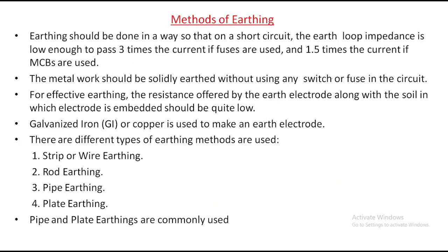Next, methods of earthing. In our electrical system, we generally have a number of methods. We will discuss each and every method. First method: earthing should be done in a way that the short circuit and earth loop impedance is low enough to pass 3 times the current if fuses are used, and 1.5 times the current if an MCB is used. The earth loop impedance should be low. When fuses are used, the earth loop impedance Z by 3, then the current will become 3 times.